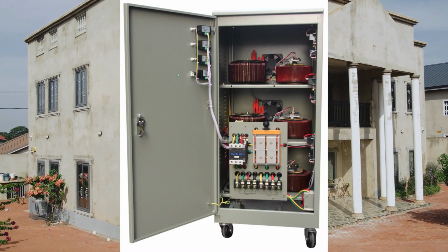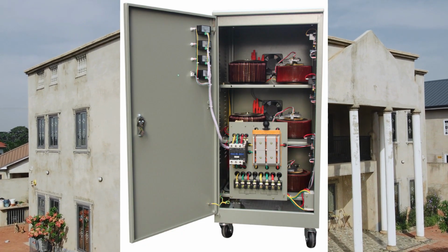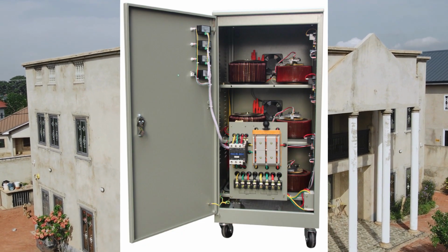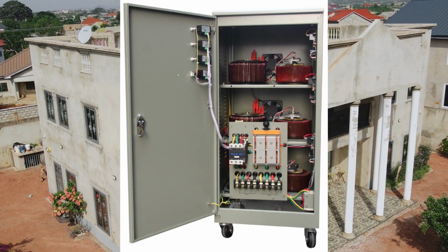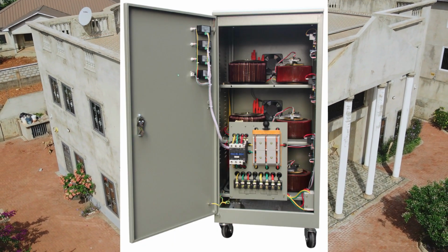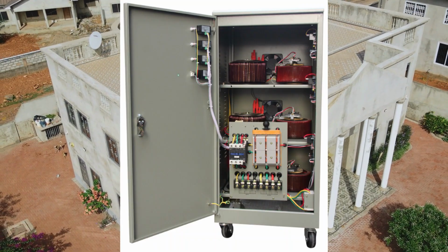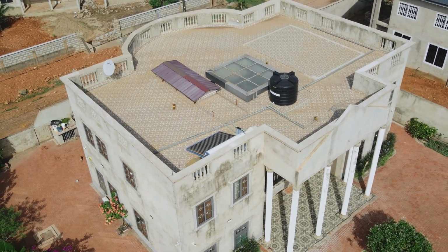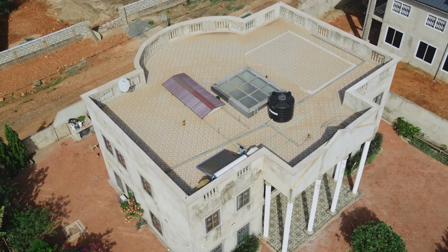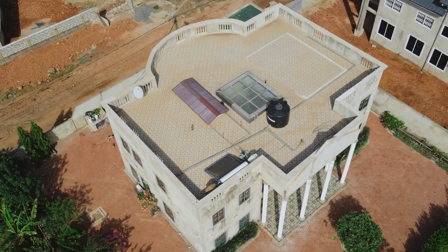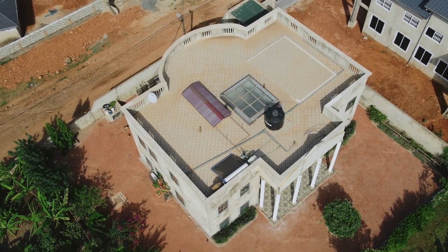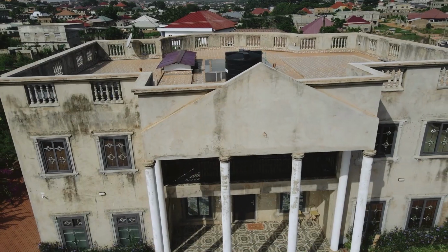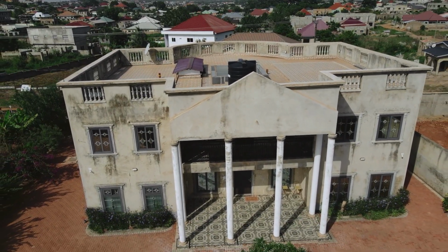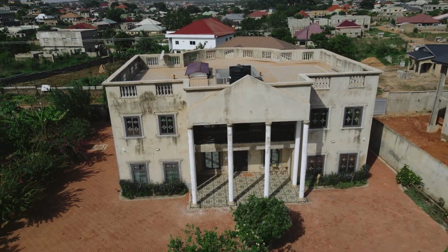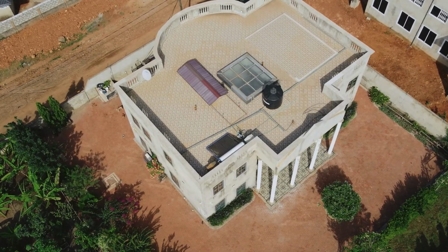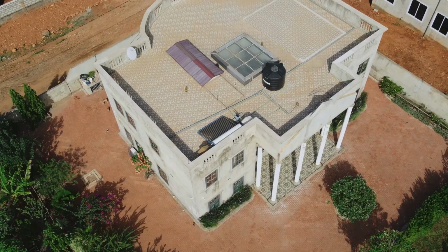When we measured each phase, the answer became obvious. Most of the heavy loads had been connected into one phase. Nearly all of the air conditioning units were on the same phase, L1. Several other heavy appliances were also connected to that same phase. The other two phases were carrying much lighter loads — lighting, a few sockets. So although the total electrical demand of the house was well within the AVR's capacity, one individual phase was overloaded. The AVR wasn't the problem, the load distribution was the problem.